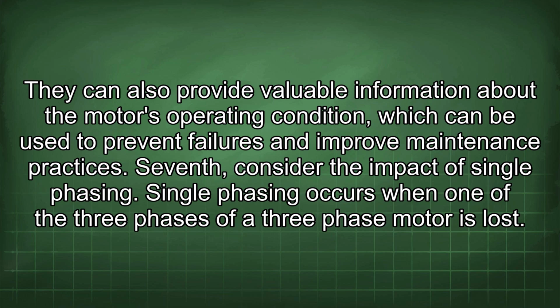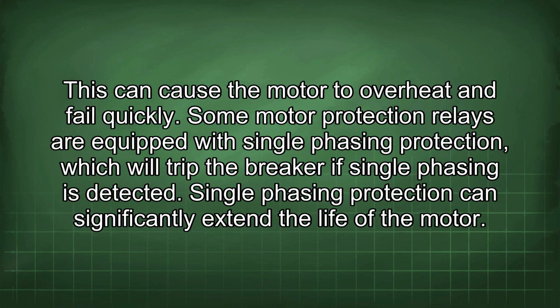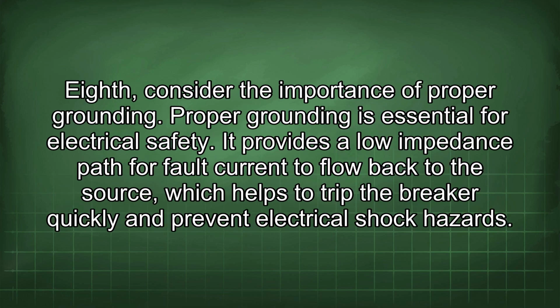Single phasing occurs when one of the three phases of a three-phase motor is lost. This can cause the motor to overheat and fail quickly. Some motor protection relays are equipped with single phasing protection, which will trip the breaker if single phasing is detected. Single phasing protection can significantly extend the life of the motor. Eighth, consider the importance of proper grounding. Proper grounding is essential for electrical safety. It provides a low impedance path for fault current to flow back to the source, which helps to trip the breaker quickly and prevent electrical shock hazards.